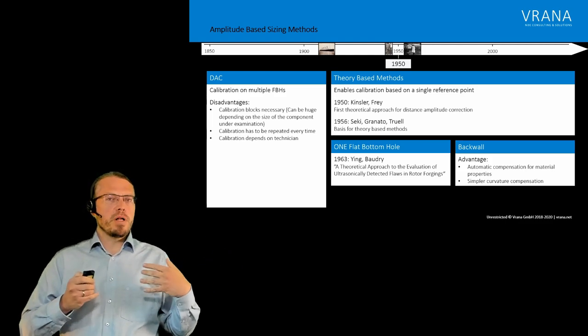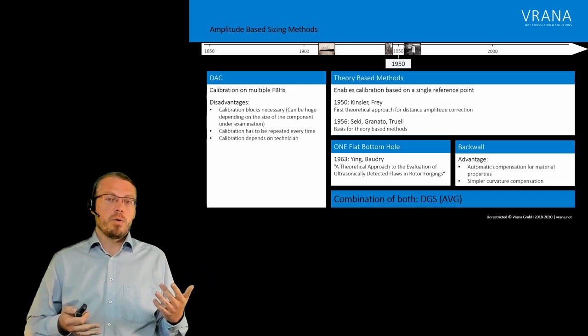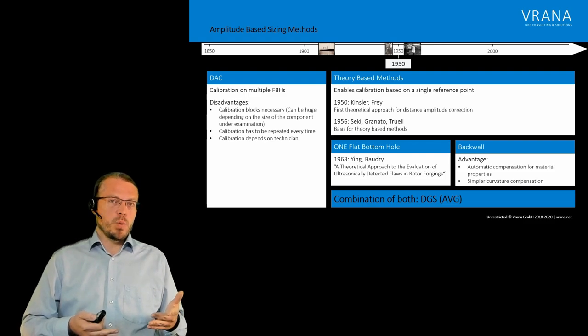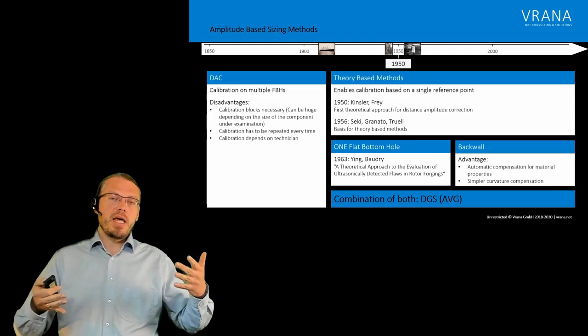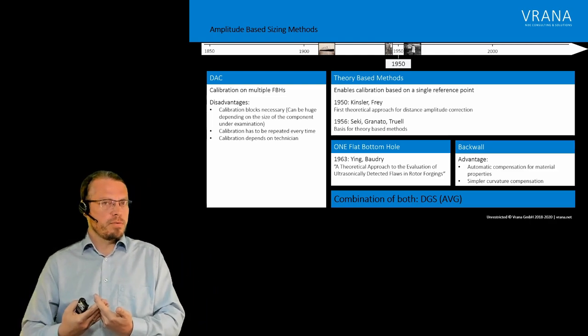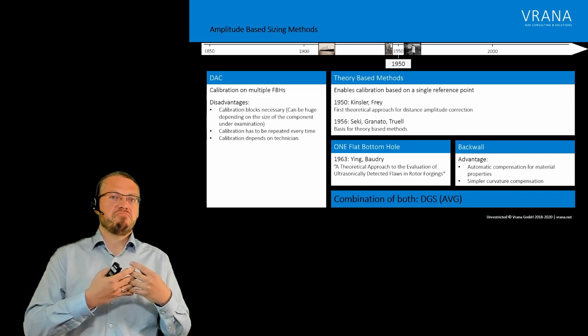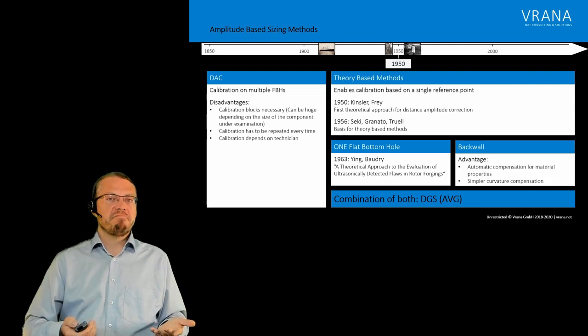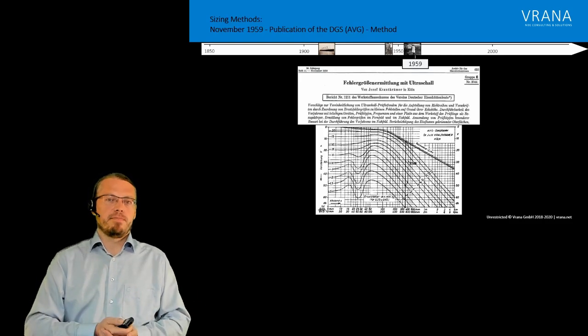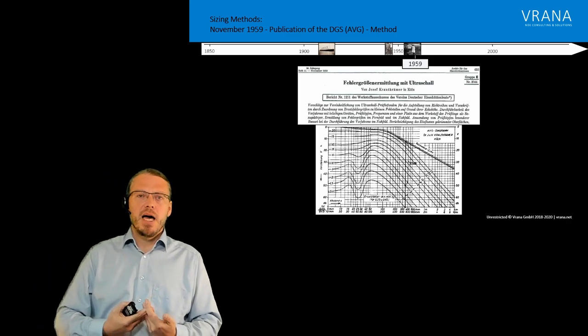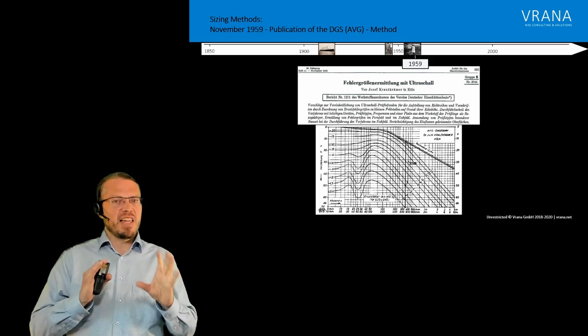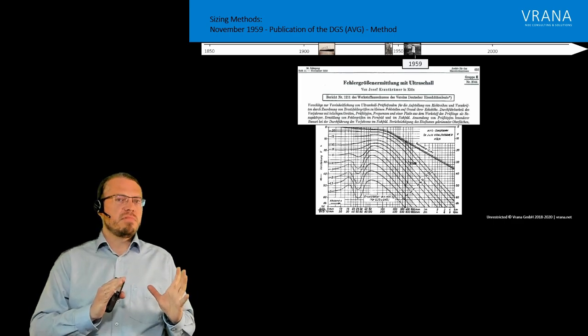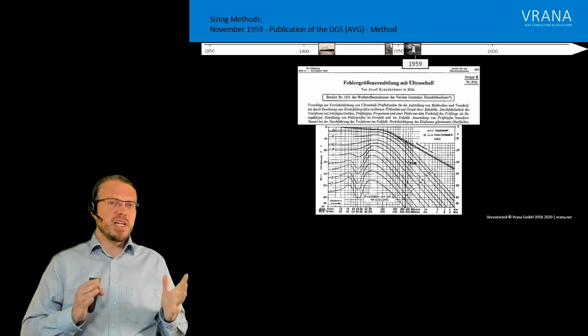Now there is one method which is very common here in the European area, which is called the DGS method. The DGS method, and what the Krautkramer brothers did back in those days, actually they took all the existing theory they knew, then combined it with a lot of experiments they did. And they produced easy to use diagrams. Now those diagrams sometimes they look a little bit challenging in the beginning. But I think I will be doing a video about them detailing a little bit how they work. Because they are actually not that complicated. And it's a really good tool.